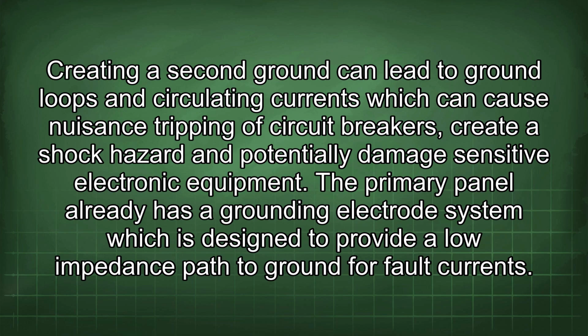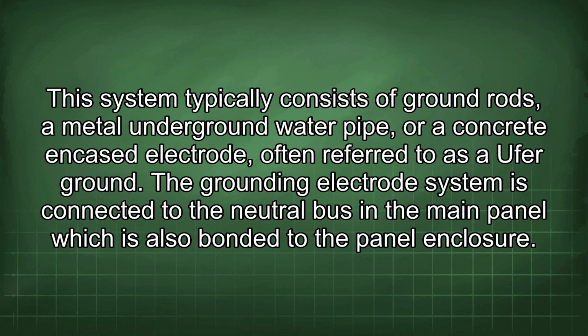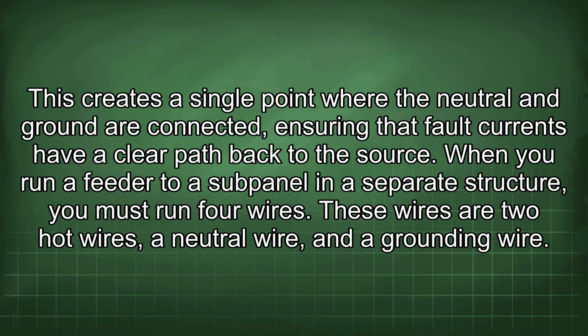The primary panel already has a grounding electrode system which is designed to provide a low impedance path to ground for fault currents. This system typically consists of ground rods, a metal underground water pipe, or a concrete encased electrode, often referred to as a Ufer ground. The grounding electrode system is connected to the neutral bus in the main panel, which is also bonded to the panel enclosure. This creates a single point where the neutral and ground are connected, ensuring that fault currents have a clear path back to the source.